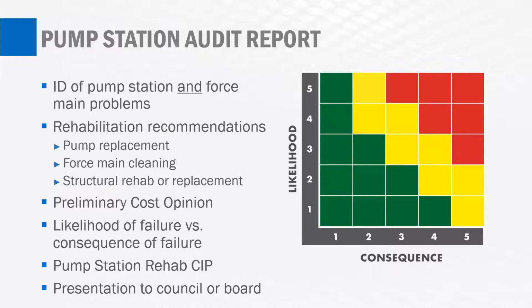One of the big ones, of course, is your pump operating the way it's supposed to. It could be a pump issue, could be a force main issue, it could be a combination of both. But does your pump need to be replaced? Does the impeller of the pump just need to be replaced? Do you just have the wrong pump in there? Sometimes what happens is utilities replace pumps and they may not replace them with the same pump that was in there previously. With force mains, is it clogged? Can the force main be cleaned through pigging, for instance? Is there structural rehab or replacement that's necessary on site?